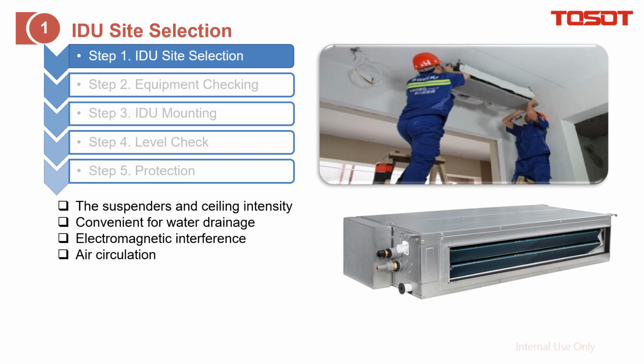This is the indoor unit installation procedure. Basically, this presentation is based on the duct type indoor unit. We will show you how we install the duct type. And basically, they are similar, whether the indoor unit is duct type, cassette, or floor ceiling. Just follow these steps and you can finish.